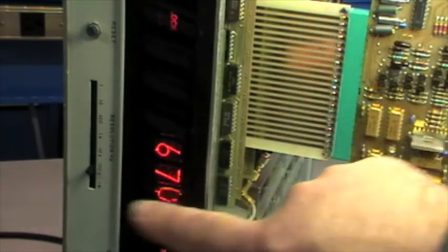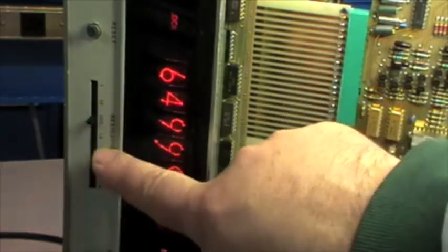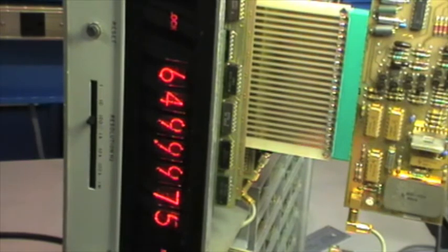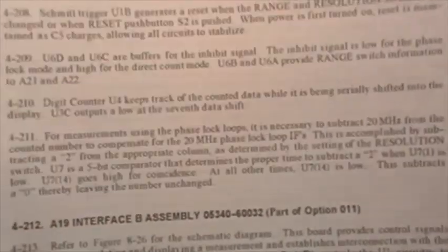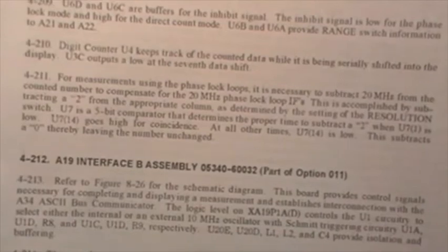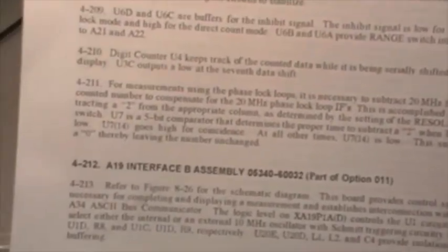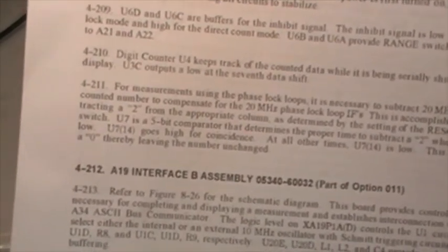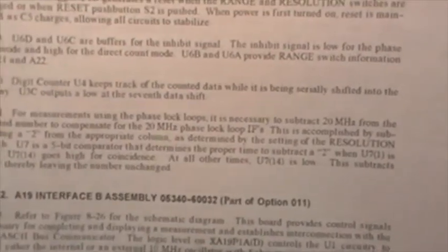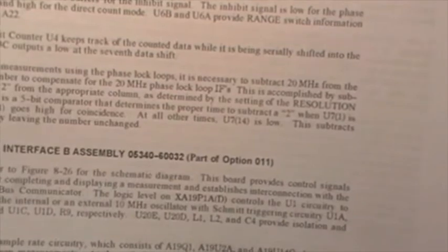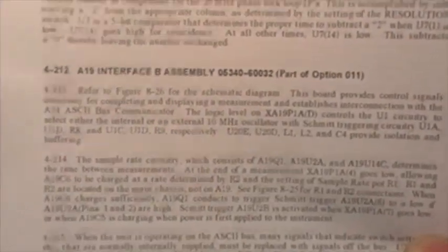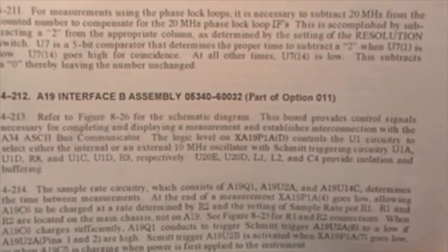the frequency shown is wrong. So I have only one range that is correct, but this does not happen in the high impedance input, which is fine on all the ranges. So this is something that should be investigated more in depth. As stated in the manual, the counting through the 50 ohm input, the high frequency, is performed using the heterodyne technique, and to achieve the right counting you must subtract 20 megahertz from the counting that has been counted at that moment.